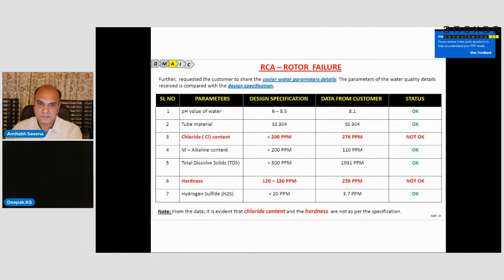Yes, further we requested the customer to share the cooler water parameter details which he recorded at site. We received the cooler water parameter details. You can see the parameters and our design specification, and the data we received from the customer. The pH value and tube material are okay, but the chloride content is not okay. It should be less than 200 ppm, and it is 276 ppm. Alkaline content, okay. Then dissolved salts, TDS, everything is okay. The hardness should be 120 to 180 ppm, and it is 238 ppm. It's not okay. So from this data, it is evident that the chloride content and the hardness are not as per the specification. Next.